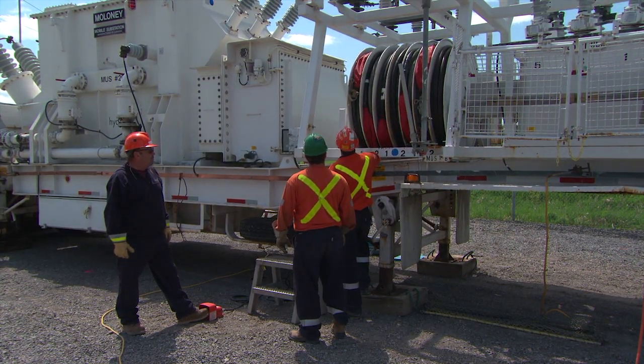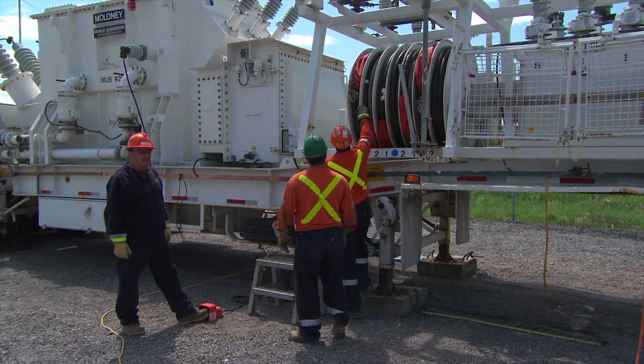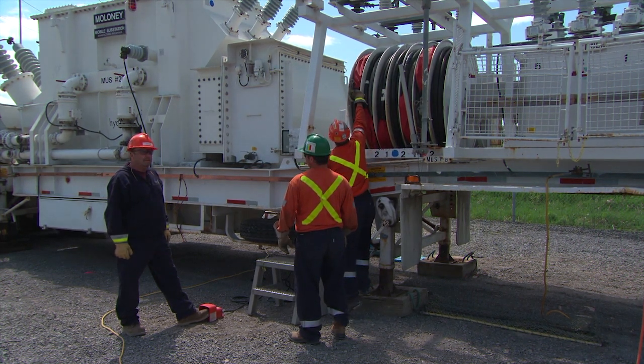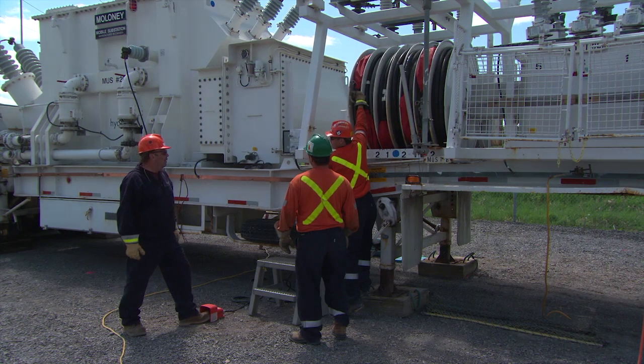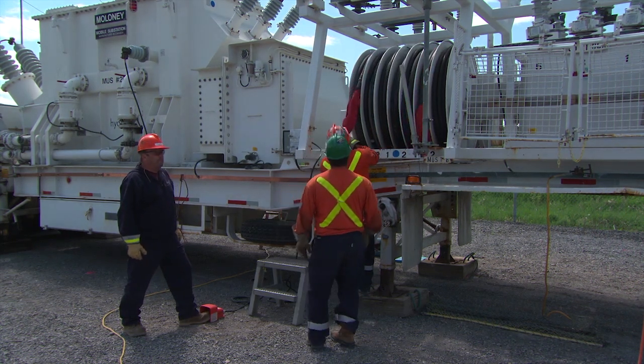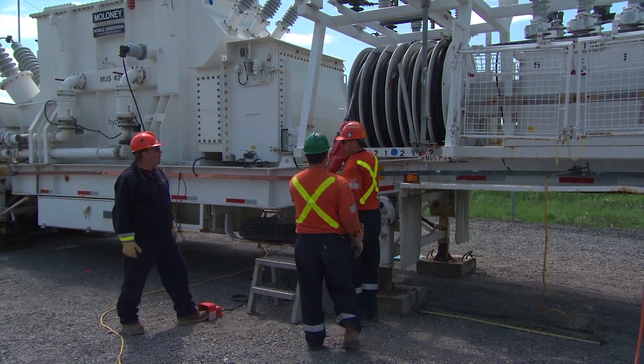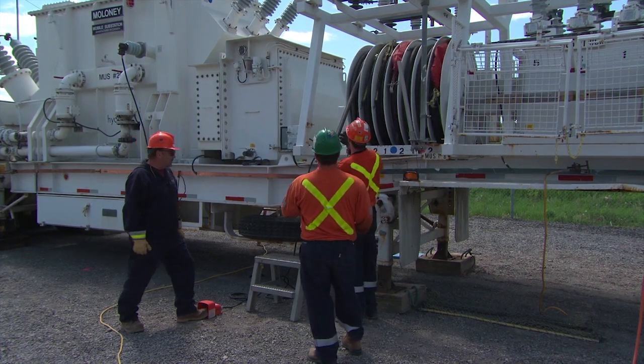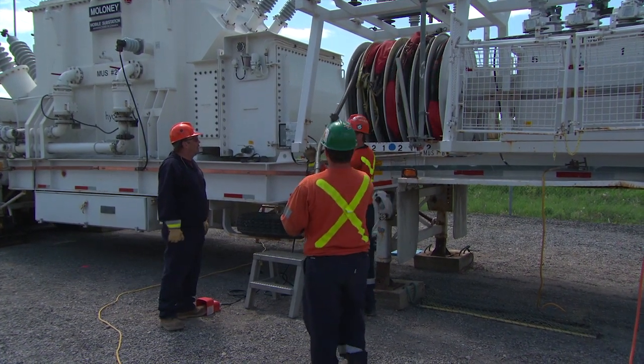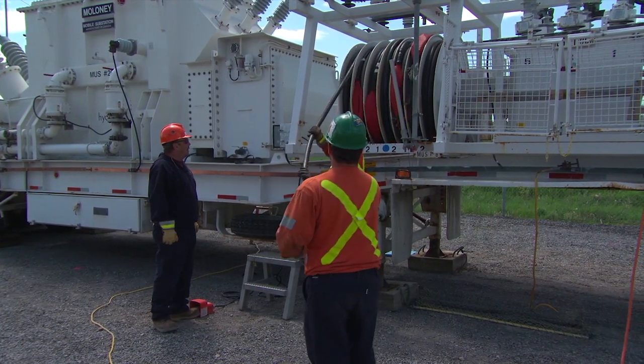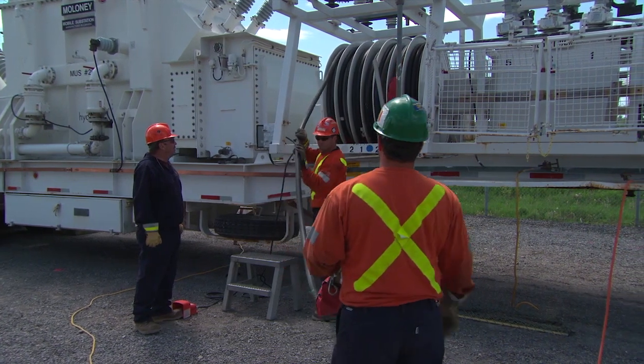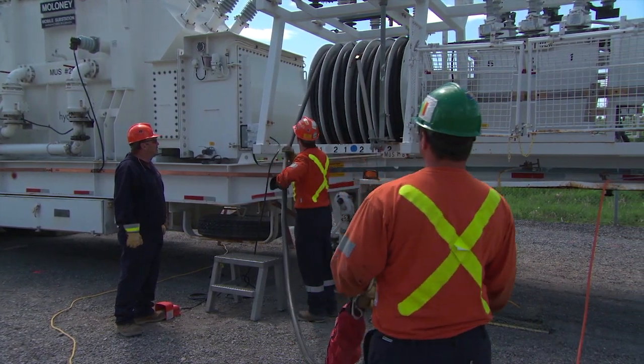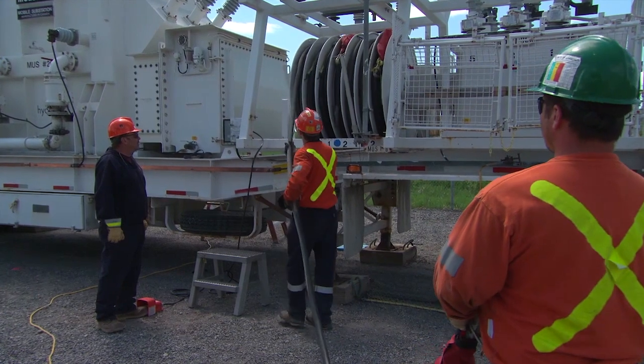Each cable and the respective ends are identified using phase marking tape. The neutral cable is identified with green tape. The F1 cables are marked red, white, and blue with a single band of tape, and the F2 cables are marked red, white, and blue with 2 bands of tape. Most mobiles have 3 sets of cables and follow the same phase identification method.